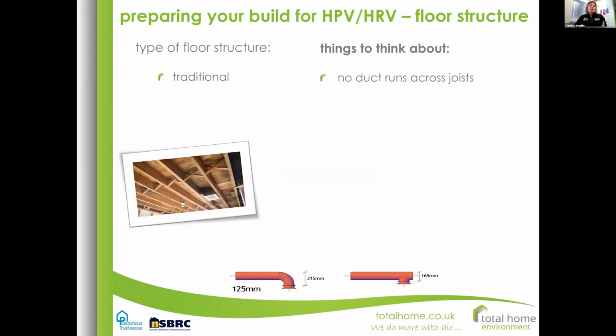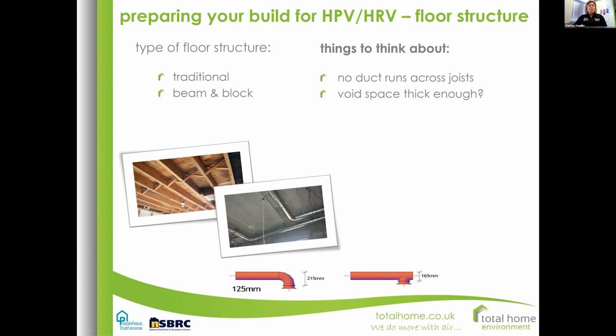So where is the ductwork going to go? Well, in a house, most of the ductwork does get lost in the floor area. But in traditional floors, if you're doing a renovation, you can only work with the joist. You can't cut across them. So you have to be slightly clever on where we would hide the ductwork to get it across to other areas of the house. Beam and block, great, but just make sure that the void depth is enough to take the 90-degree bend that comes off to the ceiling terminals. But the ductwork can go anywhere in there.